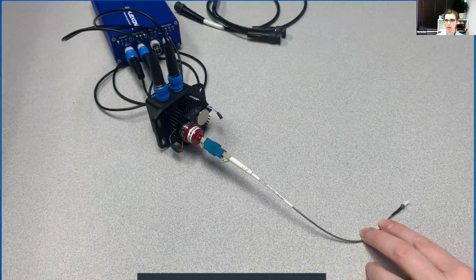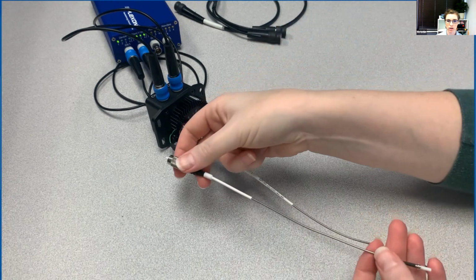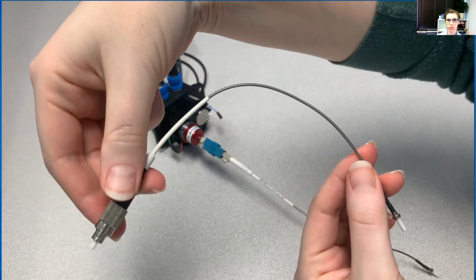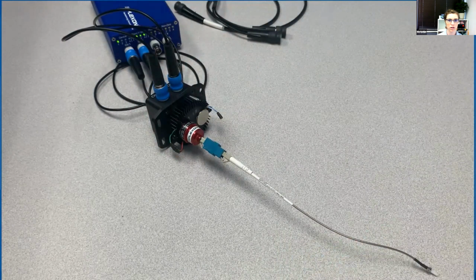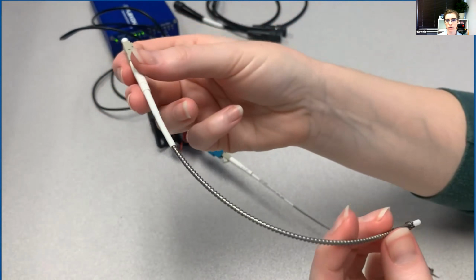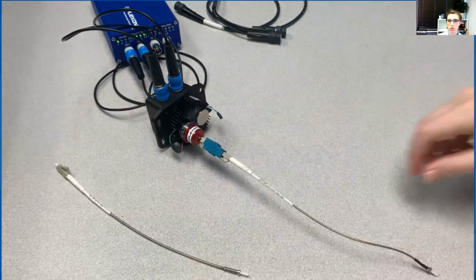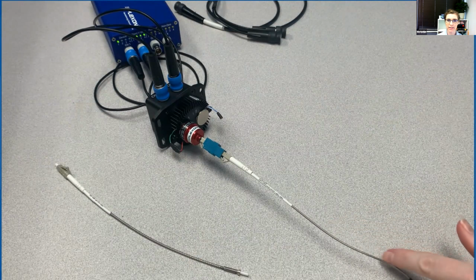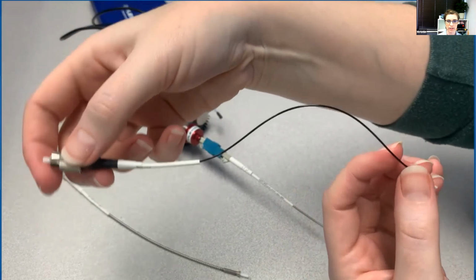And then you can turn on Radiant to deliver your pattern stimulation. This patch cable and the patch cable I showed with the in vitro setup both have a monocoil armoring, which is pretty flexible and still pretty light, and it's the minimum we recommend for rats. However, if you have a very big rat or very active rat, you can use the steel jacketing, which is much less flexible. And if you find the monocoil too inflexible or too heavy for mice, you can use a non-armored cable, which is very, very flexible and light.